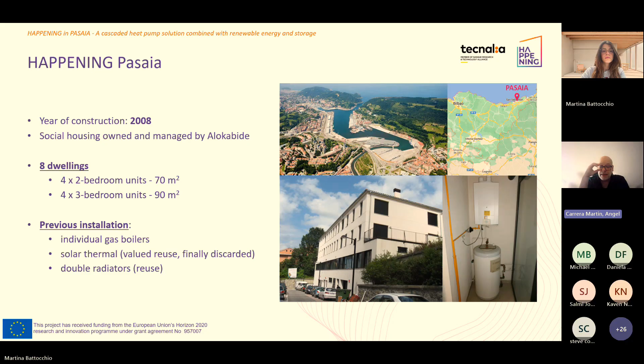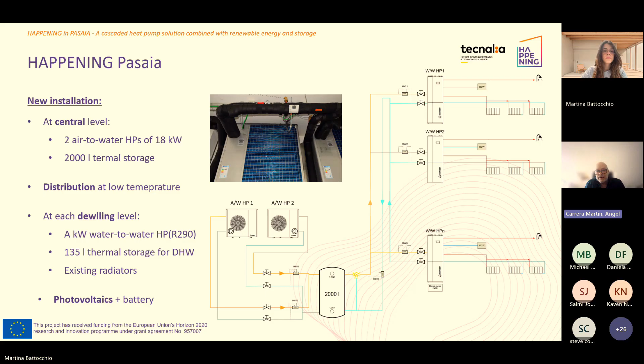So here is a brief scheme of the system. The system has 2 water heat pumps of 18 kilowatts connected to a central hot water storage of 2,000 liters, and then we distribute at something, well, it depends, but something like 20 degrees at this distribution loop. And then at each flat we have this water heat pump connected to the distribution loop, and which incorporates a 135 liters thermal storage, and then it also serves the space heating loop inside each dwelling. Then it's also a photovoltaic system with a fairly small battery.